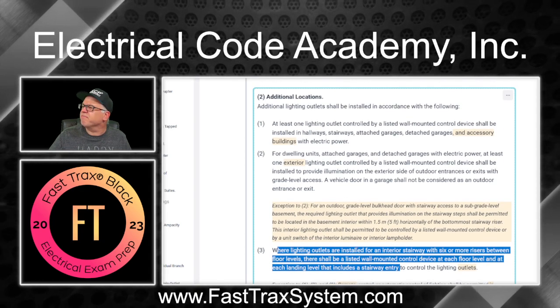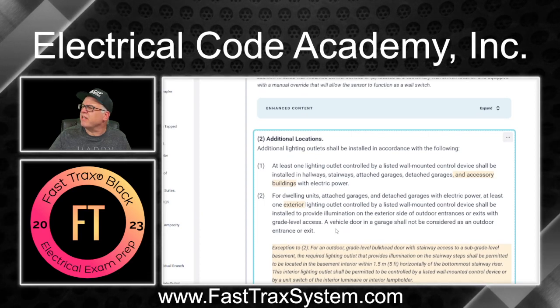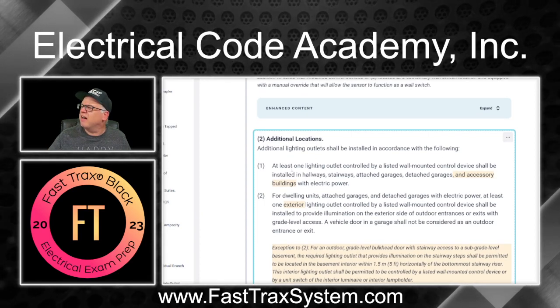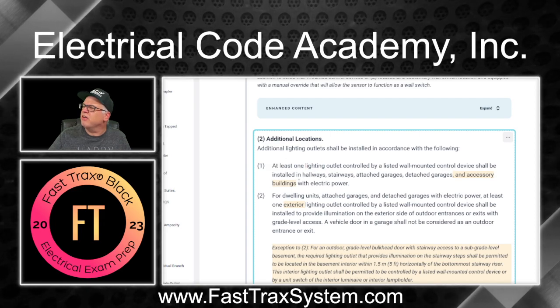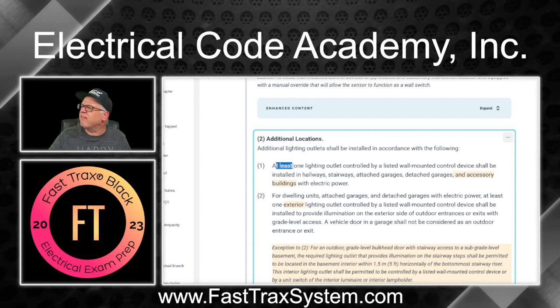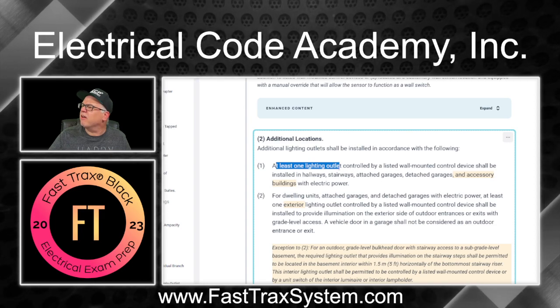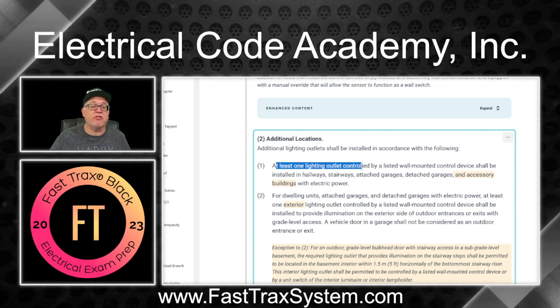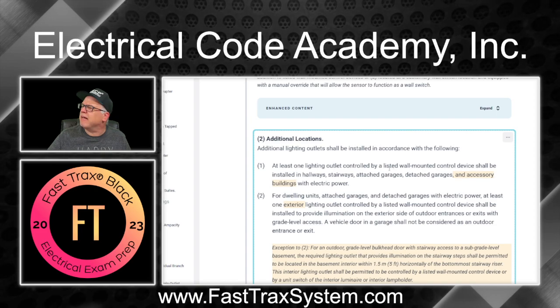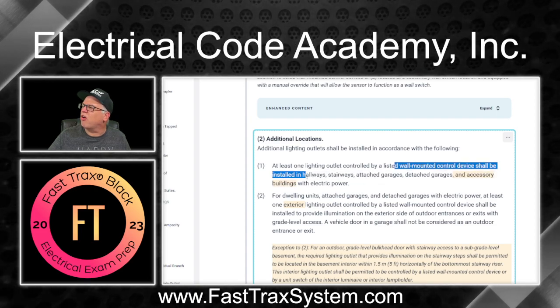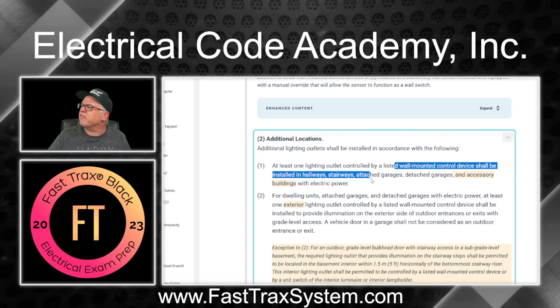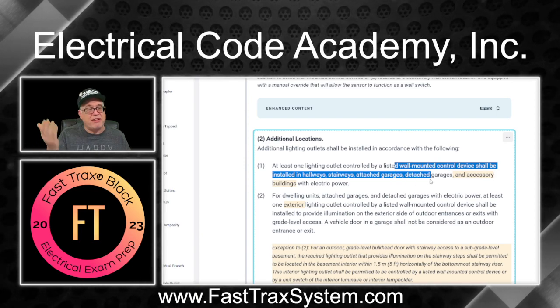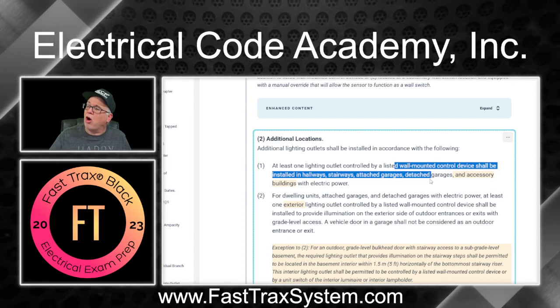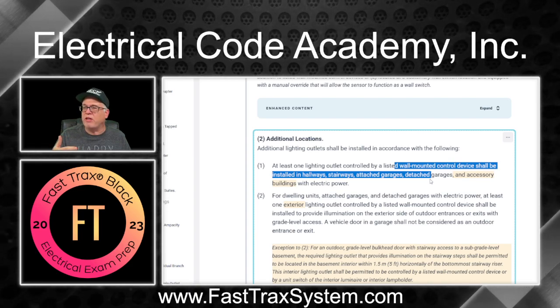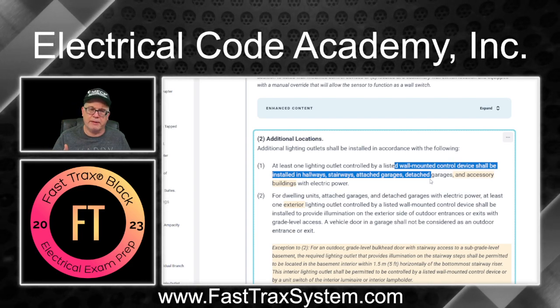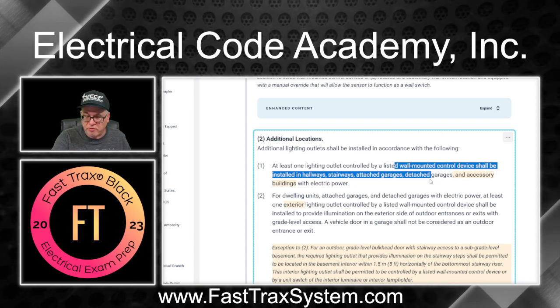How about that? Okay. Now, as far as the lighting, here's the additional requirement: you have to have at least one lighting outlet controlled by a listed wall-mounted control device, installed in hallways, stairways, detached garages. So that's the rule that requires the light there. All we did was look at the rule that requires when you have to switch it at multiple levels, and the number of risers. So that takes us back to the question.